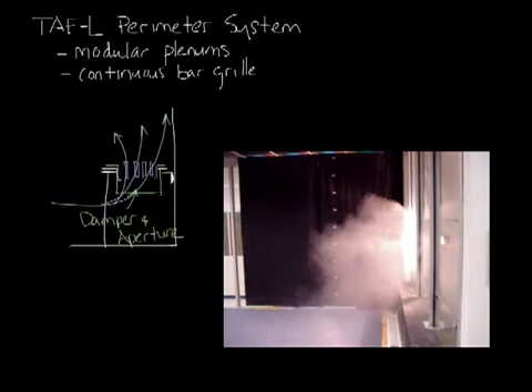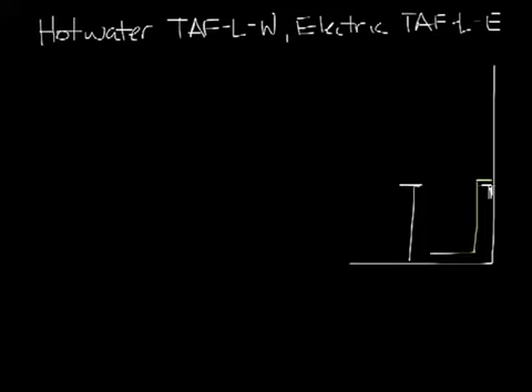Okay, so now let's talk about the heating side. The heating unit comes in a hot water or electric heat called the TAF-LW or TAF-LE respectively, and uses the natural convection currents to heat the perimeter. So again, let's draw this out in a side view. So again, this is our perimeter wall and our floor. Again, you have the angle frame and the pedestal where the raised floor starts. The TAF-LW or E will sit in here just like the TAF-LV. Then there's a divider in the middle, and the reheat coil sits towards the perimeter wall. Just like the TAF-LV, the grill sits on top.